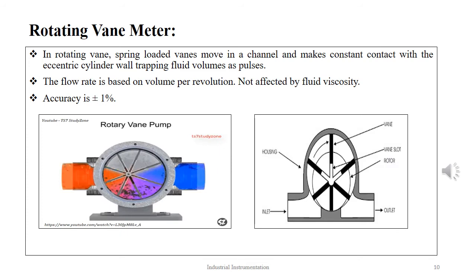The third type in the category of positive displacement flow meter is the rotating vane meter. Here, spring-loaded vanes slide in and out of a channel in a rotor so that they make constant contact with the eccentric cylindrical wall. When the rotor turns, a known volume of fluid is trapped between the two vanes and the outer wall. The flow rate is based on volume per revolution. This type is suitable for accurately measuring small volumes and is not affected by viscosity.